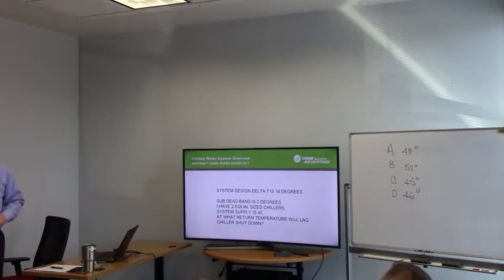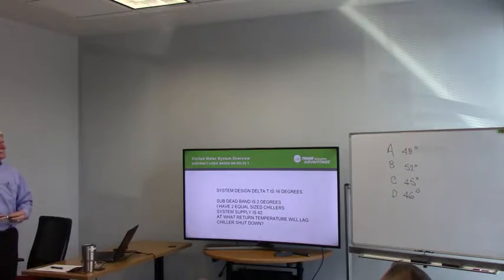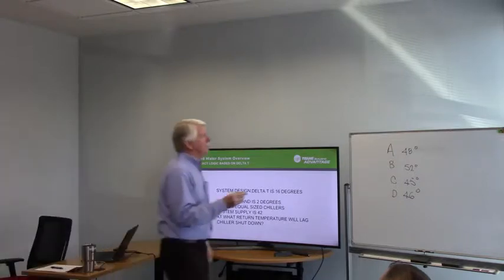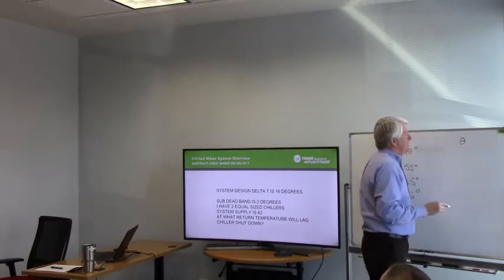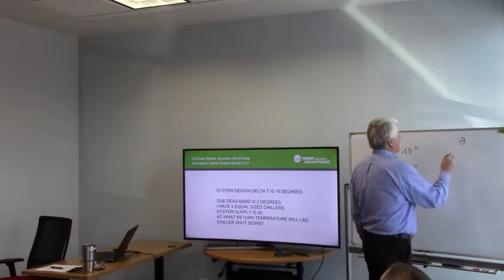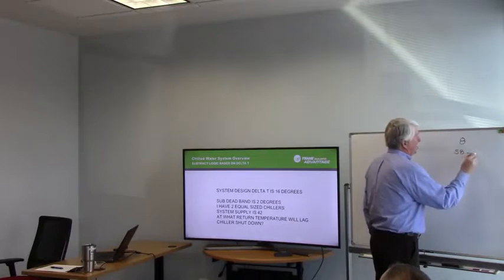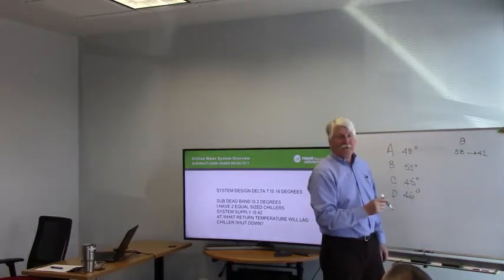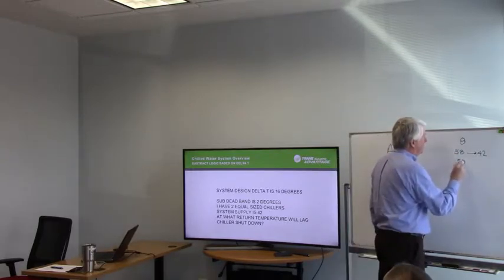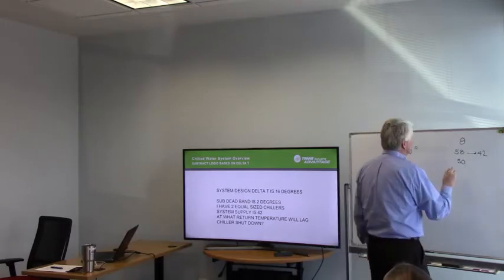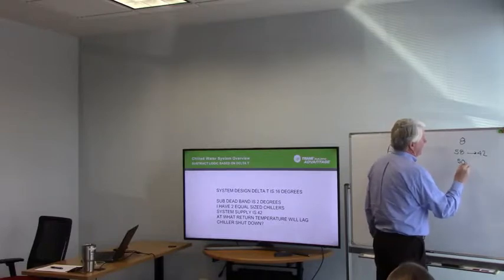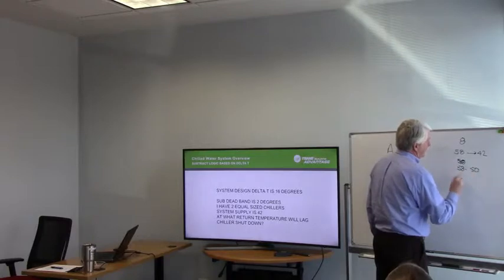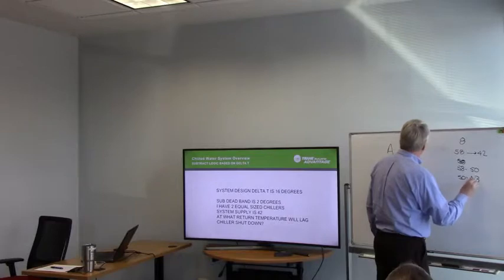So, system design is 16 degrees of delta T, with a subtract deadband. If I have equal size chillers, each chiller is going to do how much of that 16-degree work? 8. Okay? So that means if I have a 16-degree delta T, I'm going 58 down to 42, right? So now half of that, if I got an 8-degree, the first chiller is going to go 58 to 50, and the second will do 50 to 42.